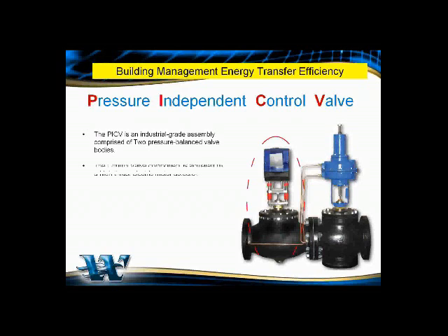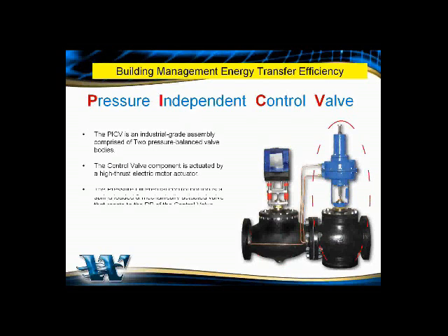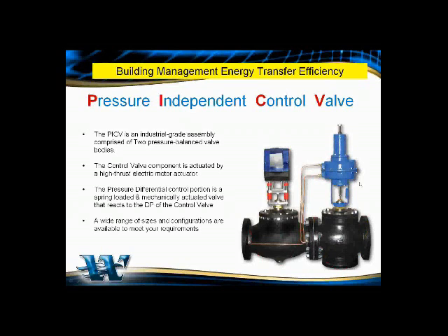The first one on the left there is actually a traditional control valve that has an electric motor actuator, and it's a very high thrust electric motor to actually control the flow. Now, if that was used by itself, that would be trying to react to the different pressures that are coming into that valve, and by itself it would not do a very good job. The second tandem valve is actually a pressure differential control valve, and it is a spring-loaded and mechanically actuated valve that reacts to the differential pressure across that control valve. So the two of these actually work in tandem, and the concept is to try to keep the differential pressure across that valve balanced. And you'll see later on, if you can control that, your energy efficiency will be improved dramatically.